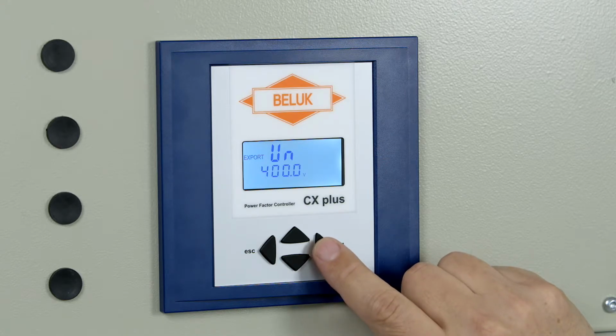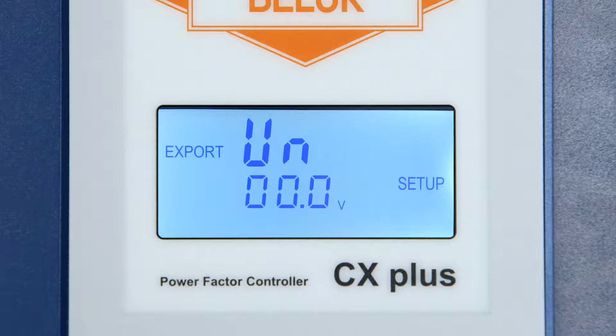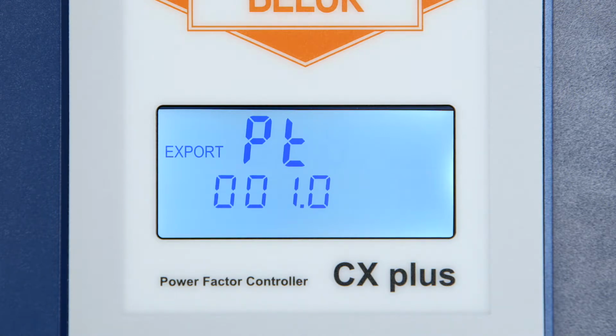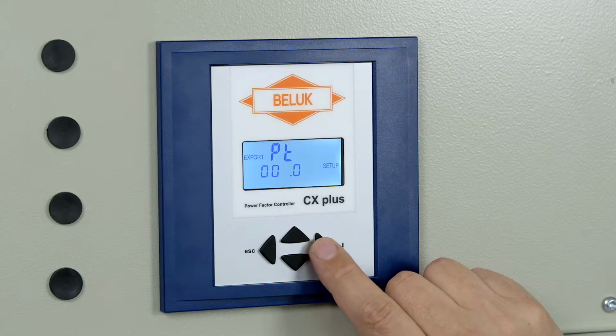First, the nominal voltage UN is queried. It can be adjusted by pressing a button or be acknowledged as unchanged. The entered value is displayed for 1 second after input. If a voltage transformer is used, then the transformer factor must be entered. If there is no potential transformer, the value remains at 1.